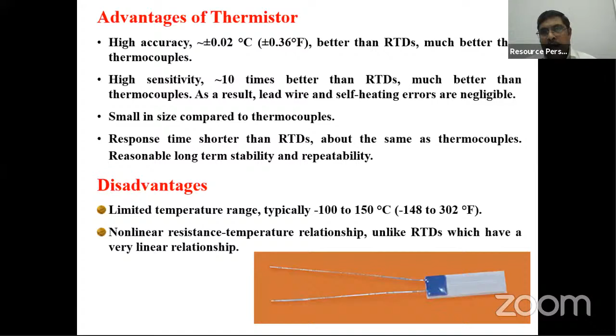For example, if your temperature range is say from 0 to 200 degrees Celsius, the same thermistor cannot fulfill your purpose. Maybe for 0 to 30, you have to use one thermistor. From 30 to 100, you have to use another thermistor. And again, 100 to 200, you have to use another thermistor. So all the thermistors have a very narrow range. That's the only problem. And so, of course, according to your application, you have to select the thermistor precisely.